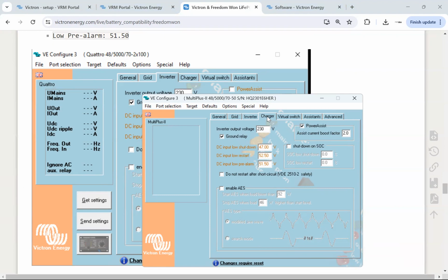Let's go to charger. Oh, by the way, don't enable AES. That's if there's very, very little power. The inverter will shut down and just pulse power every few seconds. And that's not good really for normal appliances. And it's certainly not good if you're trying to sleep and you've got an LED light and that will pulse every few seconds. That's a really old setting that was designed for being extremely conservative on power and battery systems. So even the standby power of 20 watts on the inverter would run the batteries flat because you had such small batteries. These days, for an off-grid system, that's usually not even applicable.